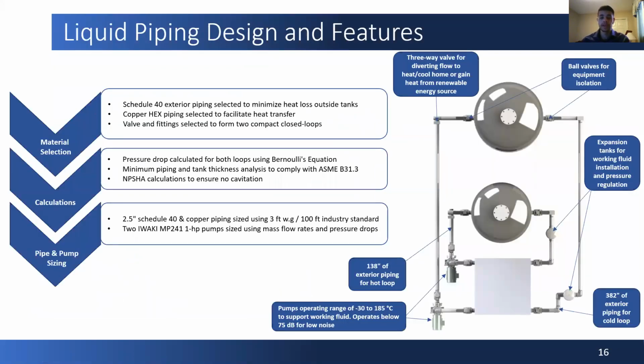For the liquid piping design, we followed 3 main stages: material selection, calculations, and pipe and pump sizing. For the material selection, Schedule 40 was used for the exterior piping, as it has low conductivity and minimizes the amount of heat loss during storage. For the heat exchanger, copper was used as it has a high conductivity and therefore facilitates heat transfer. For valves, we used a combination around all the different equipment in our system to make sure that we can isolate it and maintain it as required.